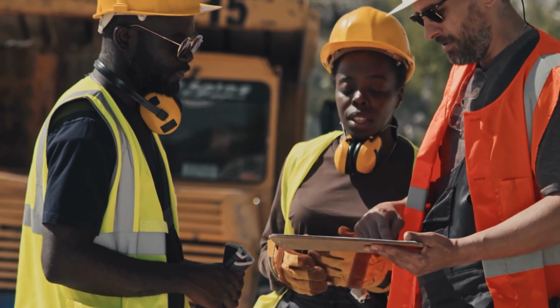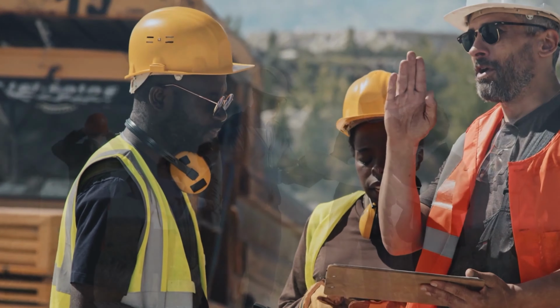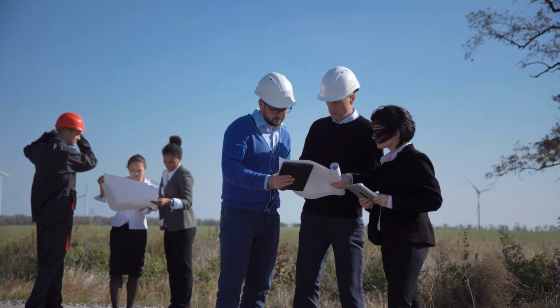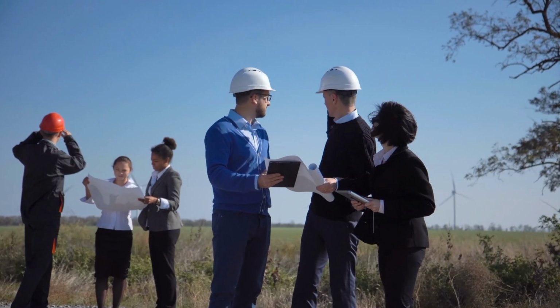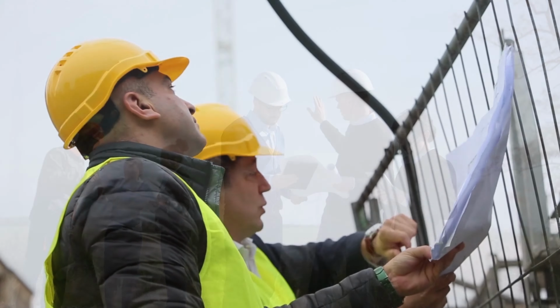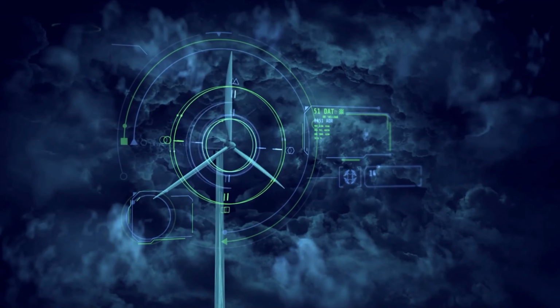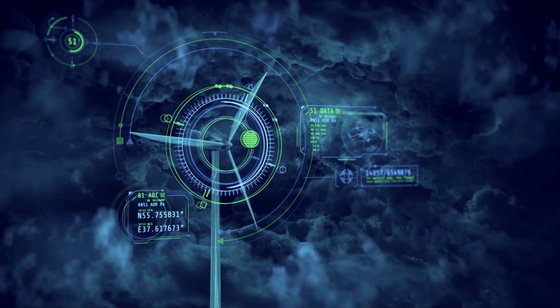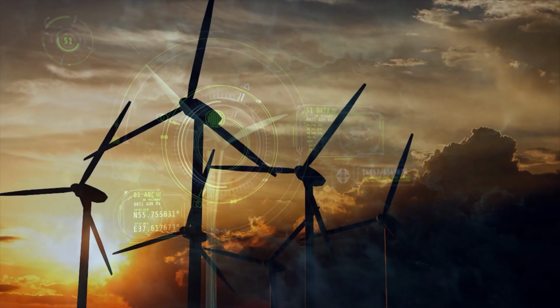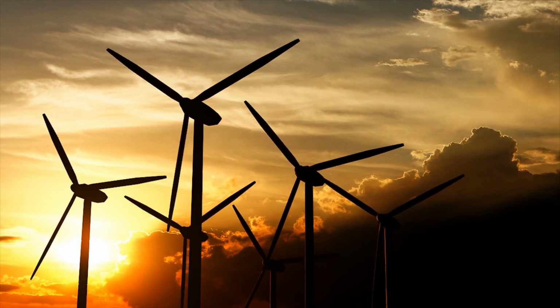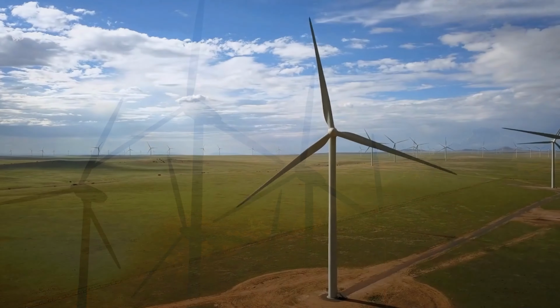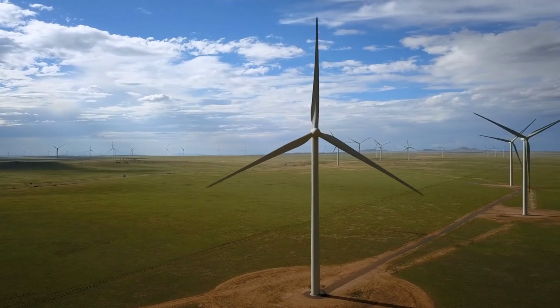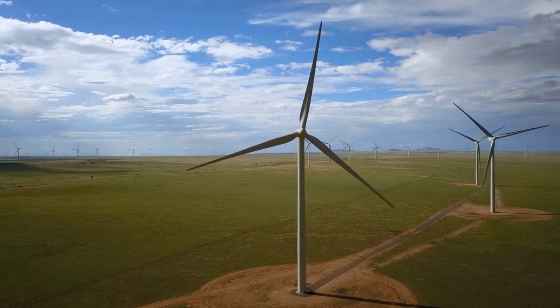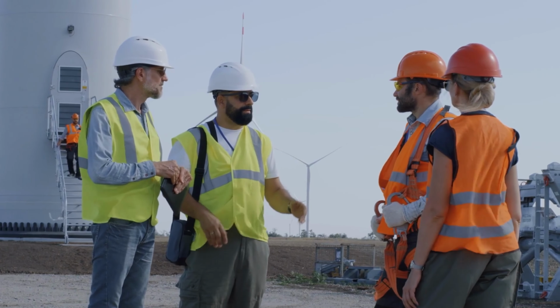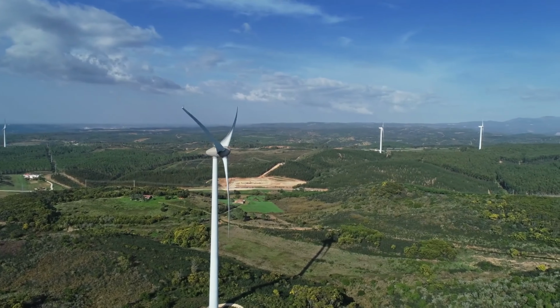Perhaps the longest part of the process is that of planning. A site survey needs to be carried out to monitor local wind speeds over a period of time, usually at least 3 months. As a guideline, for a wind turbine to be economically viable, there needs to be an average wind speed of at least 5 meters per second and in an area with minimal turbulence from surrounding trees or buildings. Planning permission may need to be granted, depending on the geographic location and usage.